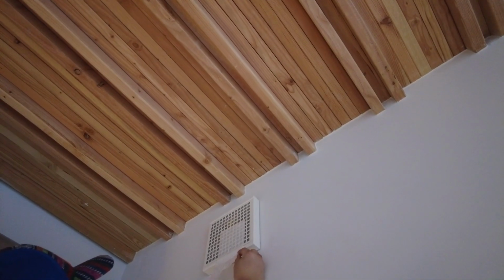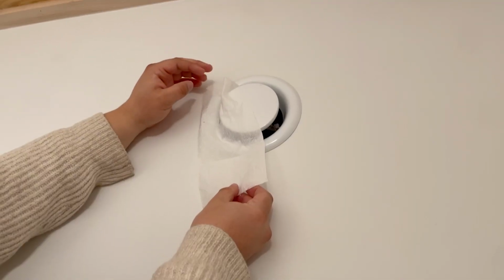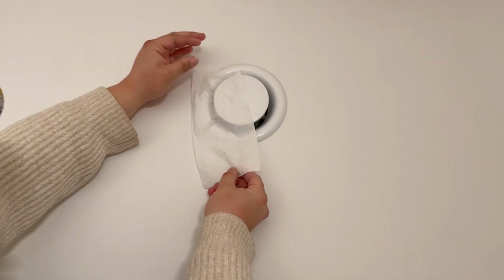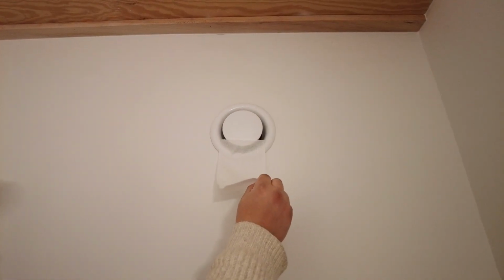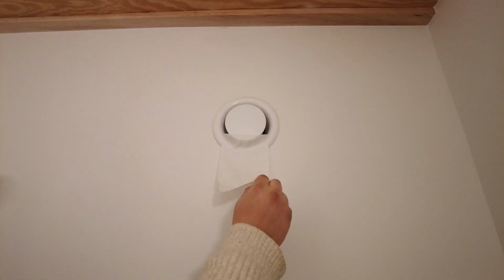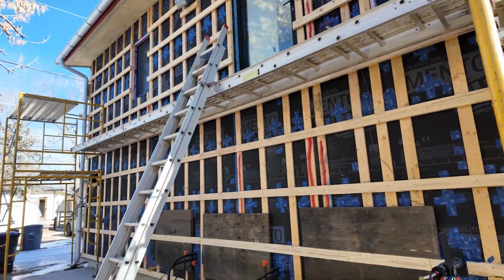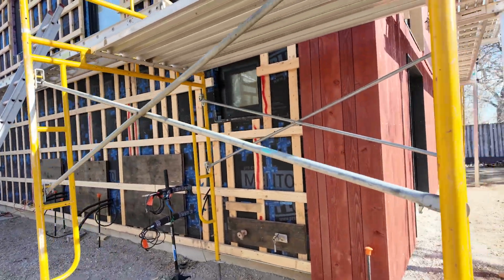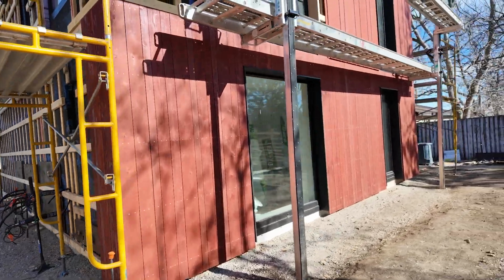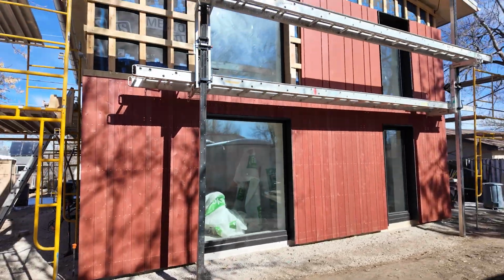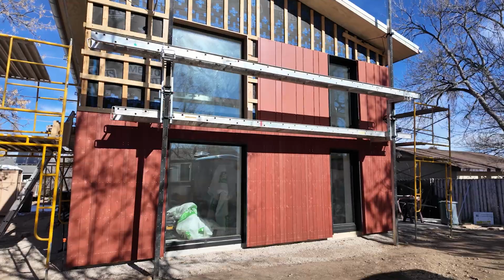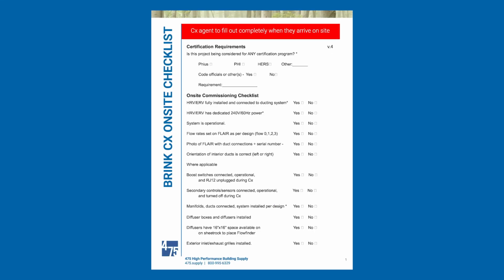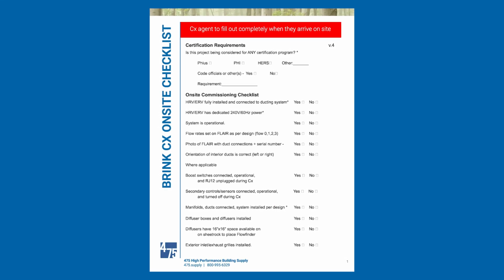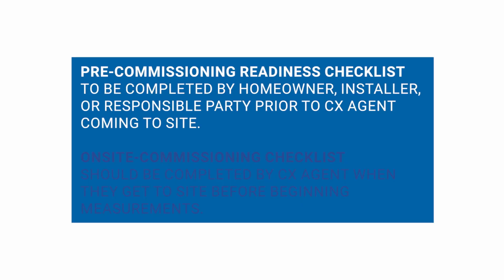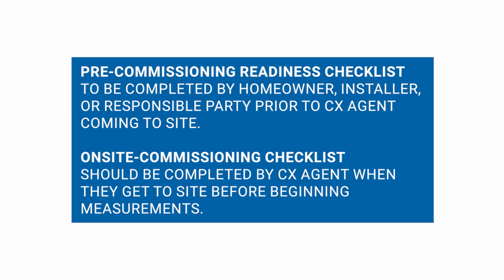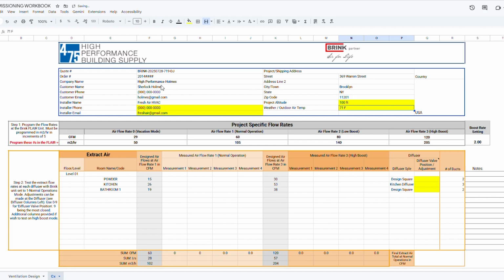A good check for large issues before the commissioning agent arrives is to use tissue paper to confirm suction is observed at extract locations and flow at supply locations. A responsible party who is familiar with the install should be present during commissioning to answer any questions about hidden ductwork, field changes, or other details critical to commissioning. When a commissioning agent first comes to site, they should also confirm the pre-checklist before getting started on the commissioning sheet. Let's look at the commissioning spreadsheet.